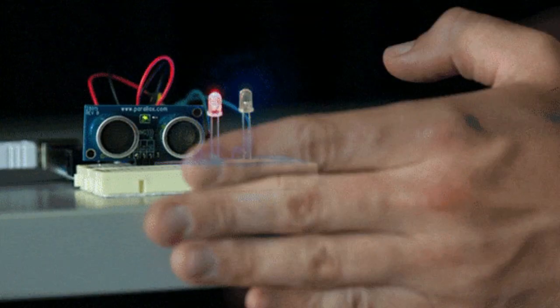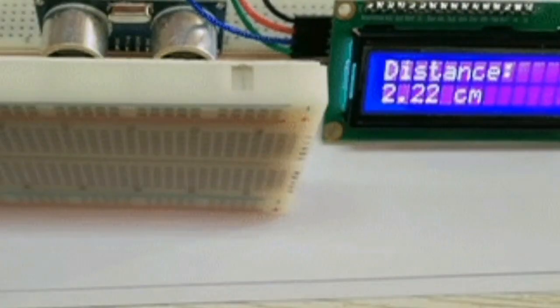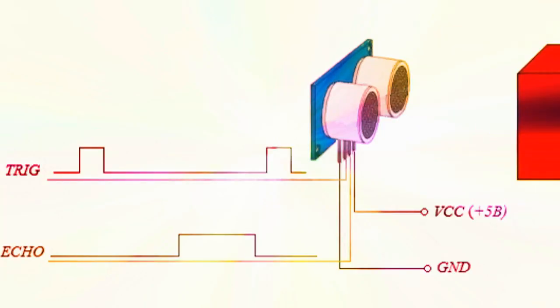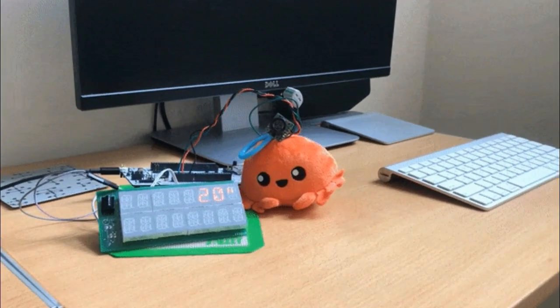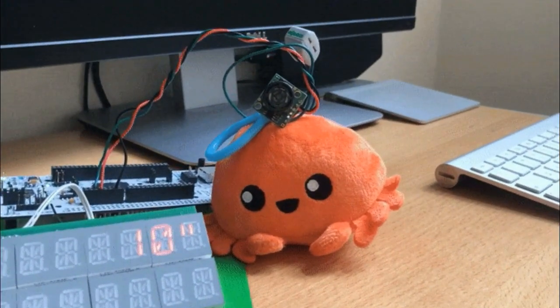An ultrasonic distance sensor detects objects in a contactless manner and measures the distance between the sensor and the measured object. To do this, it cyclically emits a short, high-frequency sound wave at the sensor head. This travels through the air at the speed of sound. If the sonic pulse encounters an object, this object reflects it back to the ultrasonic sensor. The ultrasonic probe then internally calculates the distance to the target object by measuring the time between the emission and reception of the sonic pulse.